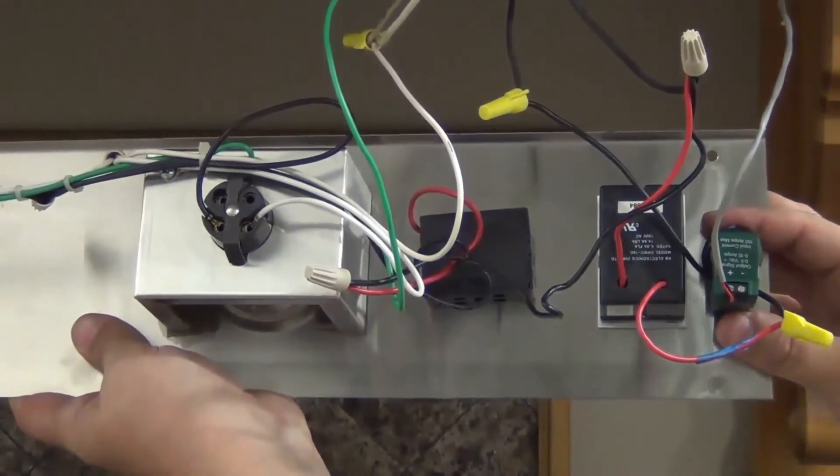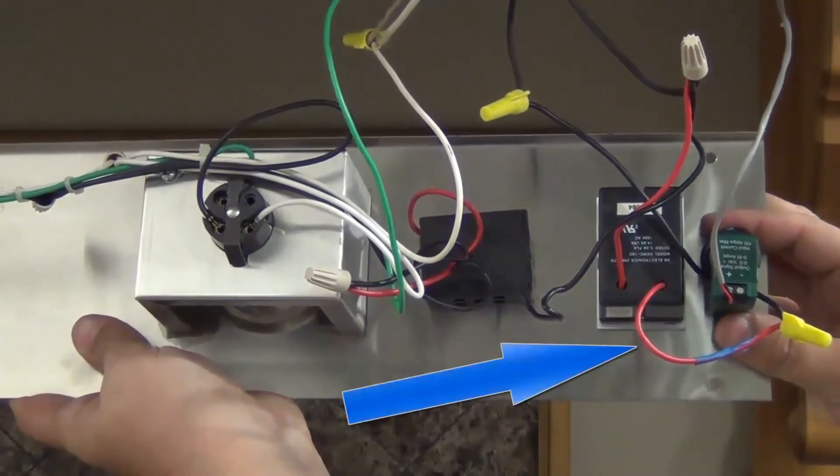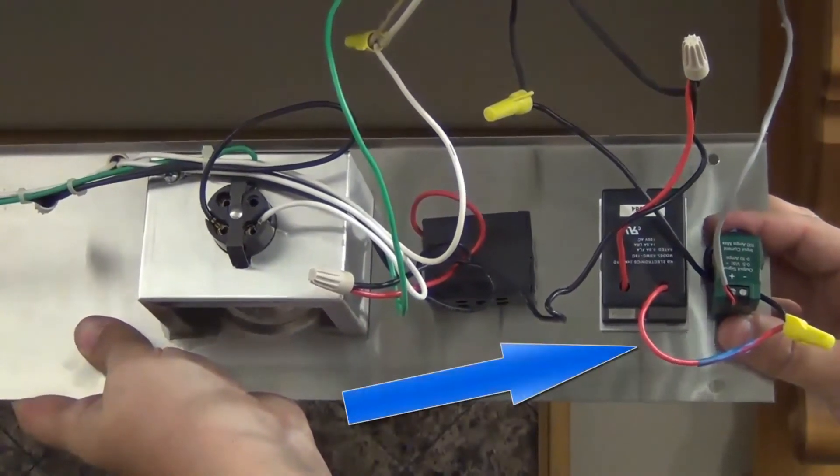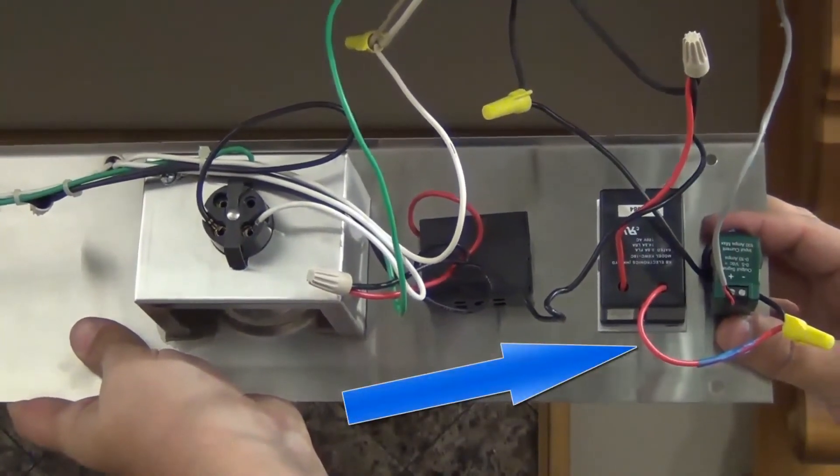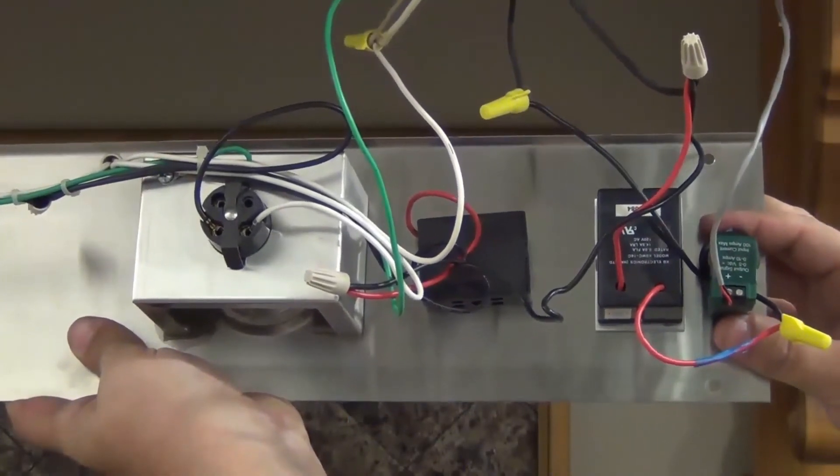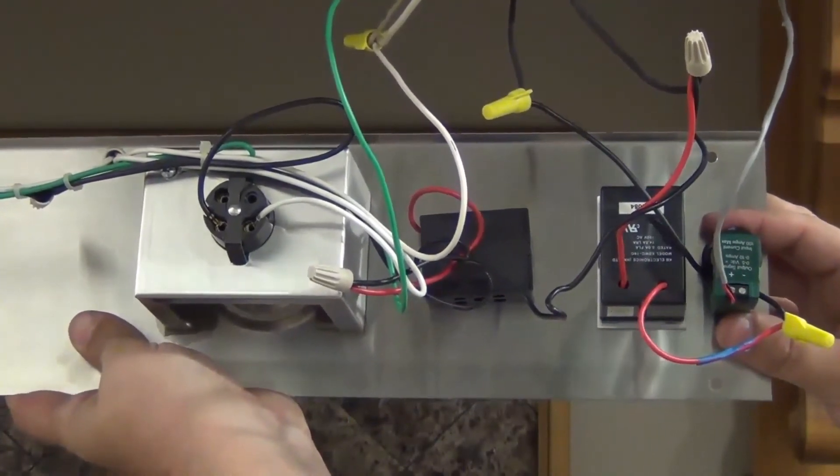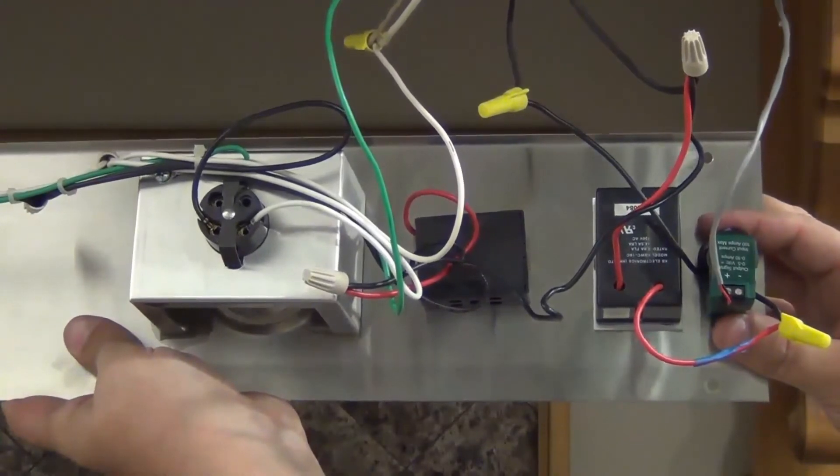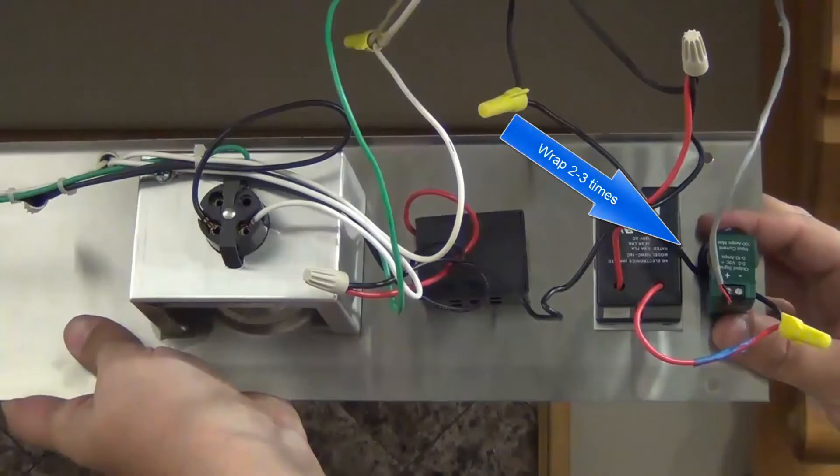The load leg of the exhaust fan speed control is installed into the transducer. However, this transducer can be installed anywhere convenient on the exhaust fan load leg. For applications with load currents less than 1 amp, wrap the fan load leg 2 or 3 times through the sensor aperture so the output will be above 1 amp.